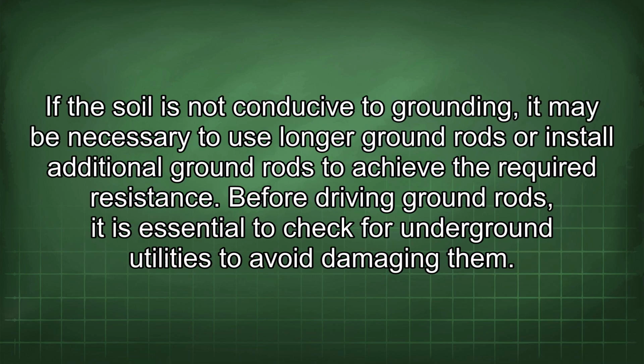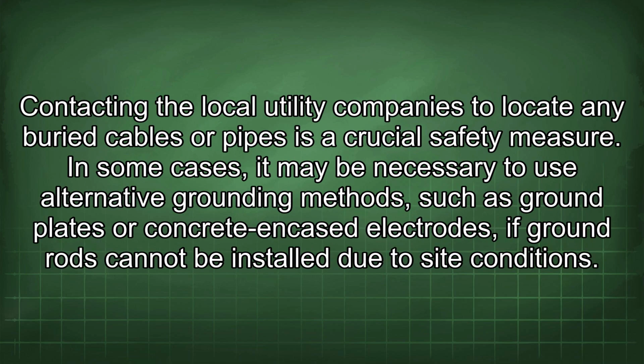If the soil is not conducive to grounding, it may be necessary to use longer ground rods or install additional ground rods to achieve the required resistance. Before driving ground rods, it is essential to check for underground utilities to avoid damaging them. Contacting the local utility companies to locate any buried cables or pipes is a crucial safety measure.